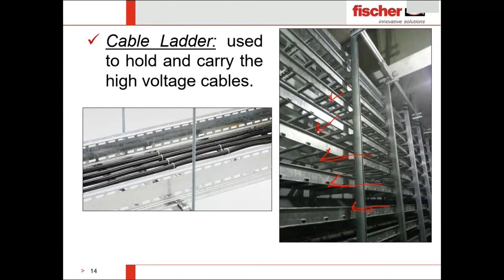After that, cable tray, which is standard and commonly used on all sites. A lot of cable tray manufacturers also manufacture supports, but unfortunately they don't check if the support is safe or not, they just go by experience - for a 600 cable tray, use a spacing of 2 meters and a channel of 40 by 40 millimeters. This is pure experience, not always 100% correct since it can vary based on conditions we'll explain later. So it's not just about fixing a cable tray - here you can see channels, threaded rod, and anchor bolt, three components.